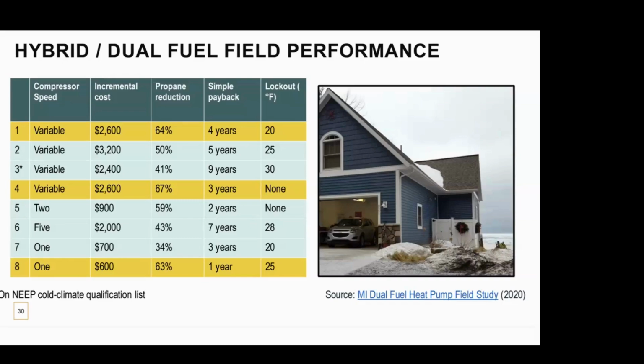Below that on sites 5 through 8, given that single and dual stage heat pumps are cheaper, that marginal cost difference tends to be less than an inverter heat pump. Pairing these units with a propane furnace, from the baseline propane furnace you're able to see a reduction in propane usage anywhere from 34% to up to 67%, which is huge. So you're maximizing the air source heat pump for when it makes sense economically, and then the gas furnace when it's more advantageous to do so.